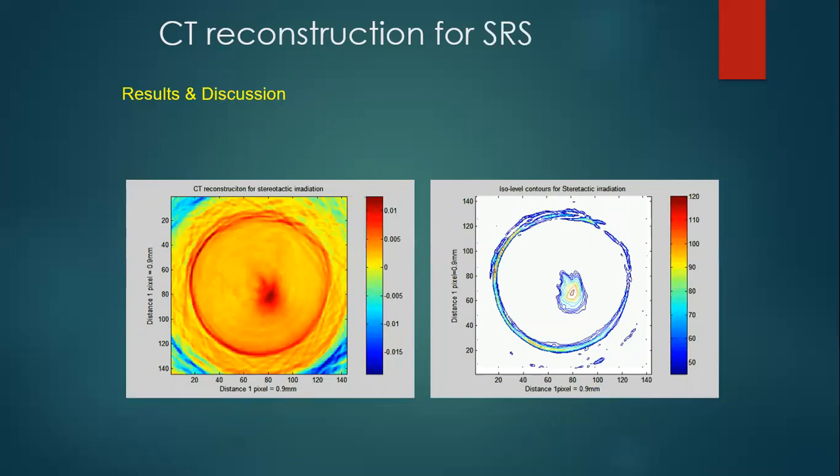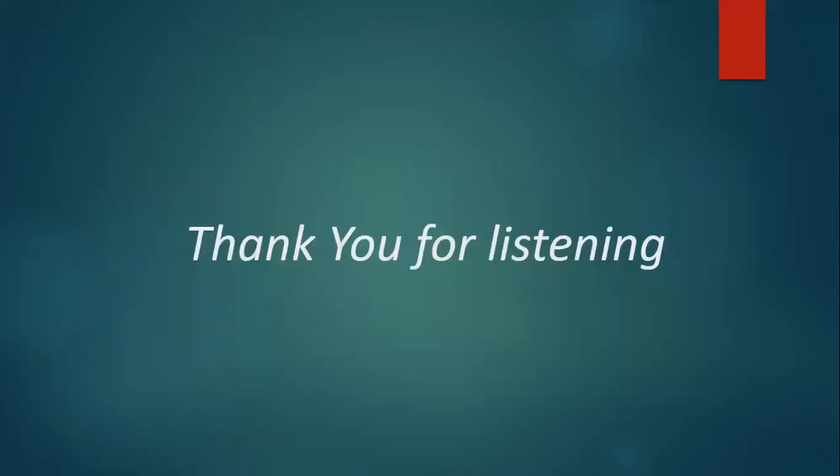This is the story of my first optical cone beam CT scanner. I presented it at a DOSGEL conference in Belgium, and they were really impressed by how we used very simple means to develop it. Now we have a very good upgraded system with a 540-nanometer light source, an industrial camera, and an FDK-based cone beam reconstruction algorithm written by our own students. We also implemented CUDA for parallel processing, so all 400 slices of the entire gel phantom can be reconstructed in less than a minute. We also calibrated it for dose and can export to DICOM format to the MimVista software and compare with the TPS — gel dosimetry.